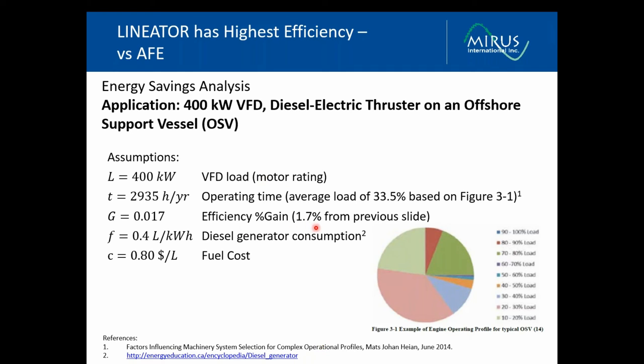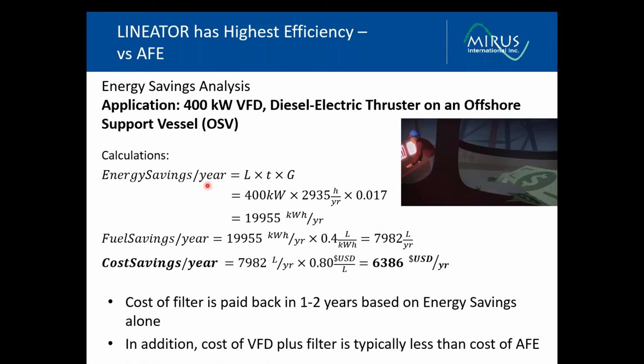We have the efficiency gain of 1.7%. If we look at diesel generator consumption as being 0.4 liters per kilowatt hour and a cost of diesel fuel of 80 cents per liter, then you can see that we go through the calculations. There's a savings of almost 20,000 kilowatt hours per year, fuel savings being almost 8,000 liters per year, and a cost savings of over $6,000 per year.